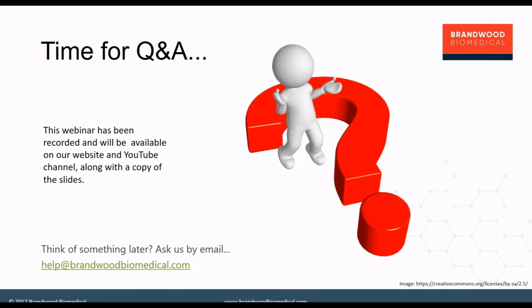Okay, so I've got another question here from Brett. Should the technical file include the design input document? Typically, no. So the technical file includes essentially all of the outputs.